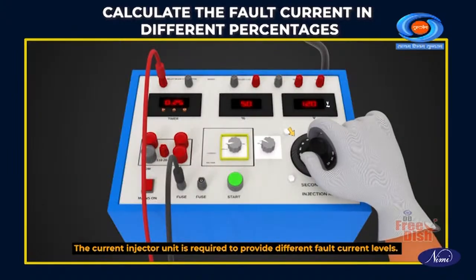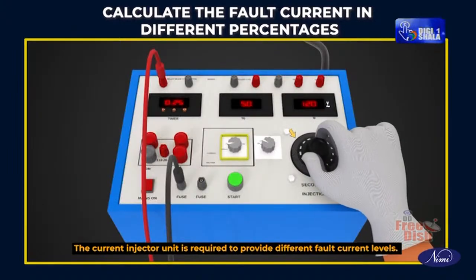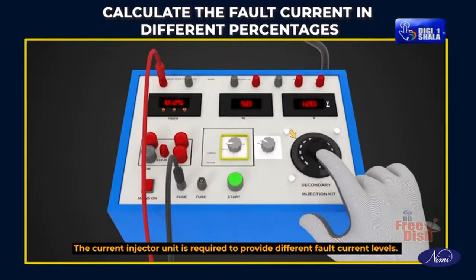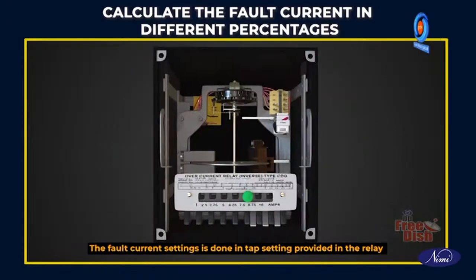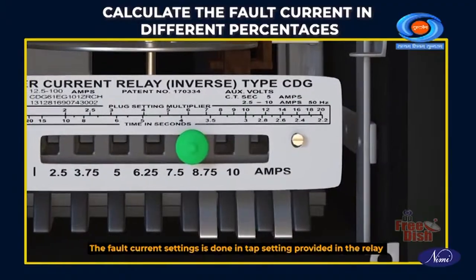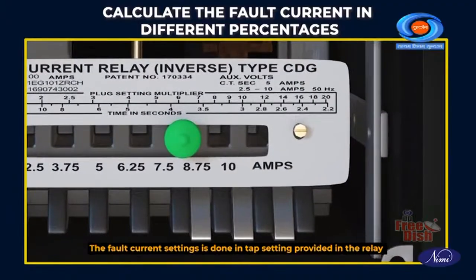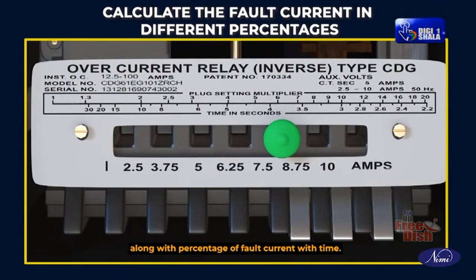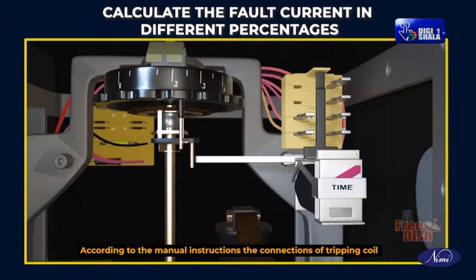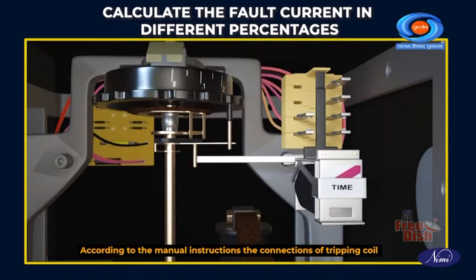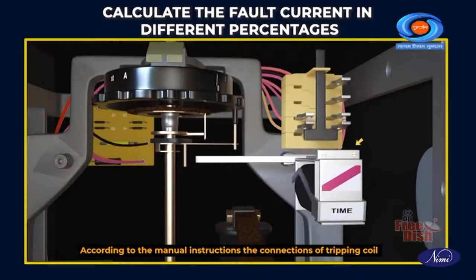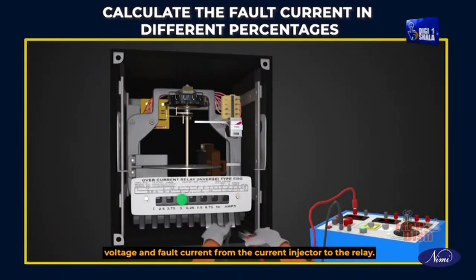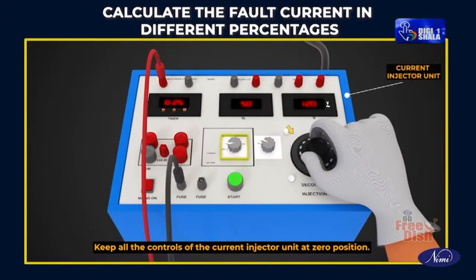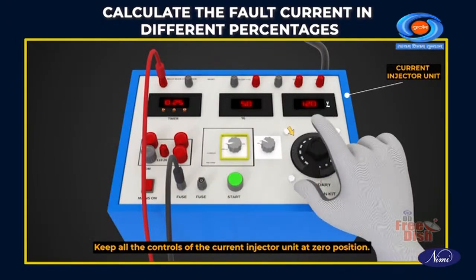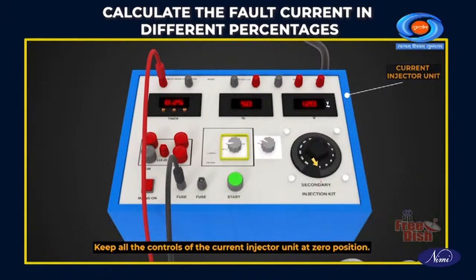The current injector unit is required to provide different fault current levels. The fault current setting is done in the tap setting provided in the relay, along with the percentage of fault current with time. According to the manual instructions, make the connections of tripping coil voltage and fault current from the current injector to the relay. Keep all the controls of the current injector unit at 0 position.